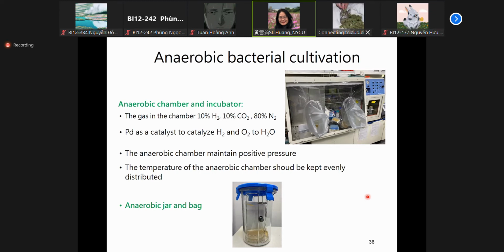the gas in the chamber, this is a representative, typical percentage, is 10% hydrogen, 10% carbon dioxide, 80% nitrogen. To remove the trace oxygen, palladium is a catalyst to catalyze the formation of water from hydrogen and oxygen, and therefore to remove the trace amount of oxygen that goes through the system. As you can see here, there's a small chamber to allow you to put your stuff here for a while, and then open the chamber here by using this to control the gas inside.